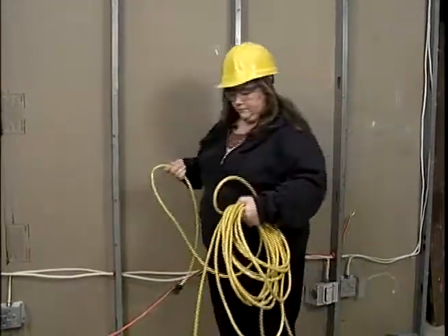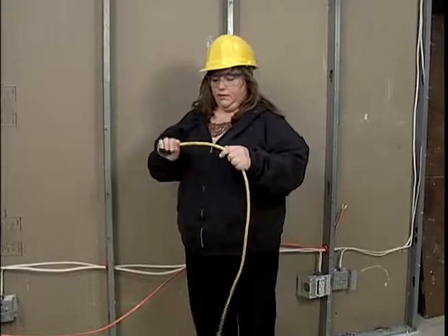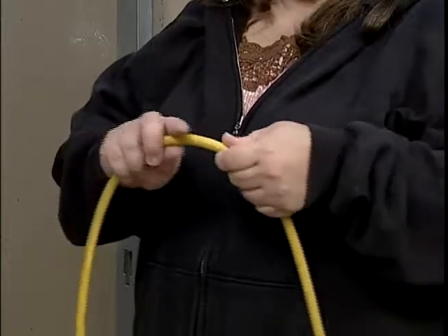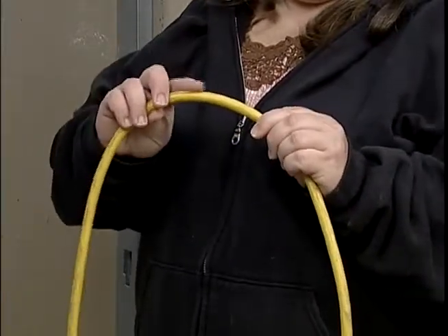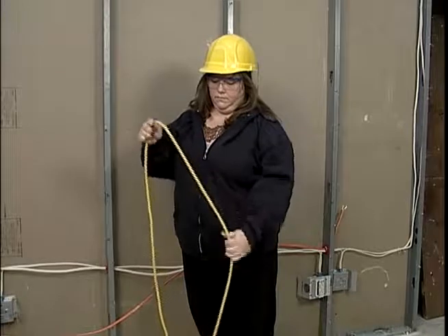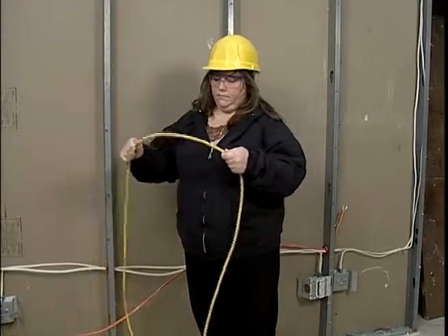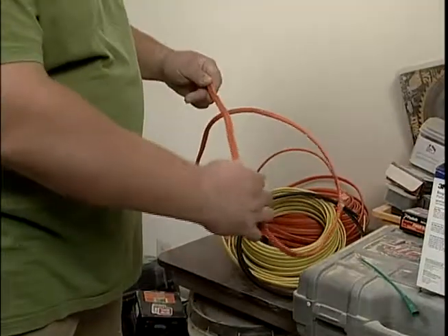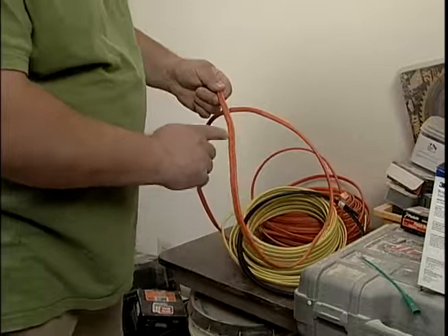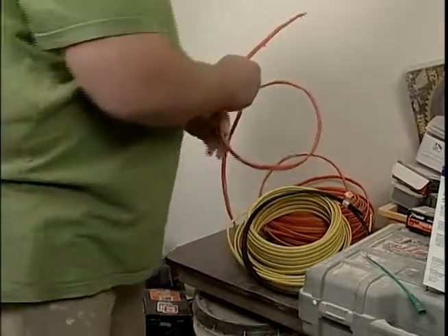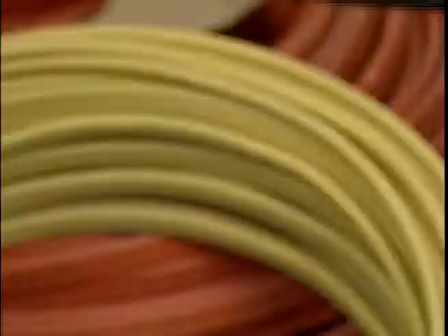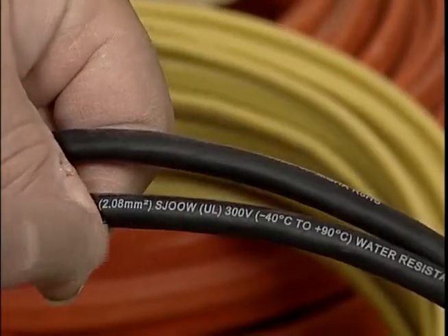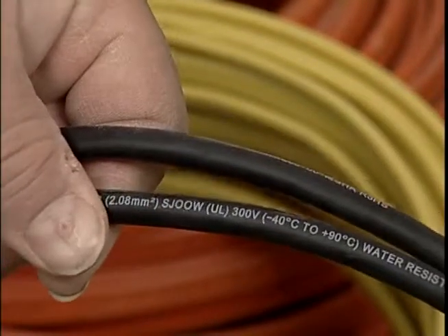Lastly, OSHA requires that employers ensure that the flexible power cords and extension cords that are used on their job sites be rated for hard or extra hard usage, as determined by the National Electrical Code. These ratings must be indelibly marked on the cords, approximately every foot along the length of the cord. Codes that are commonly found on cords indicating that they are suitable for hard service include S, ST, SO, and STO. Cords indicating junior hard service include SJ, SJO, SJT, and SJTO.